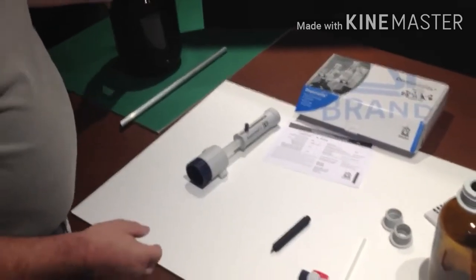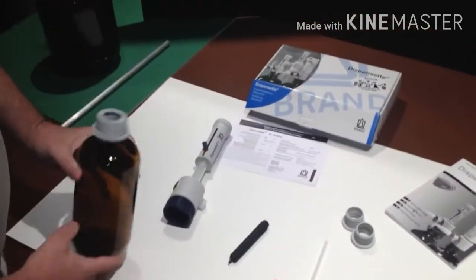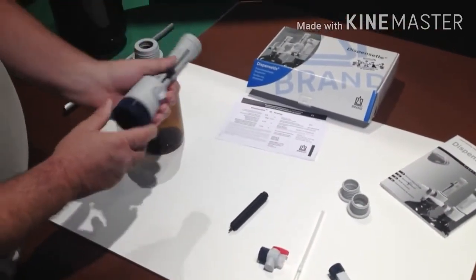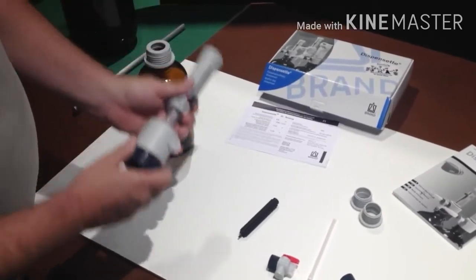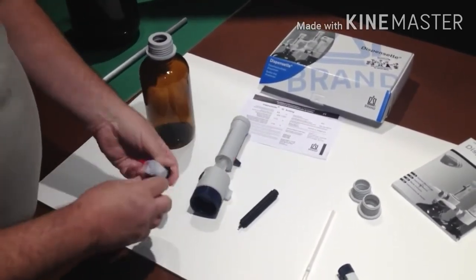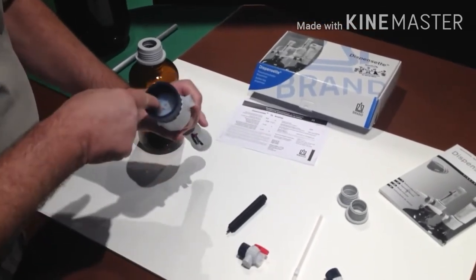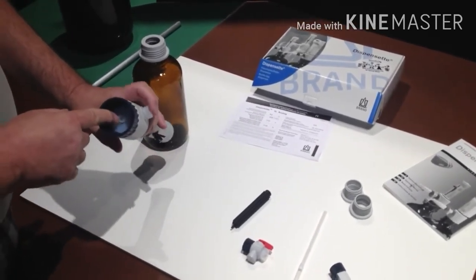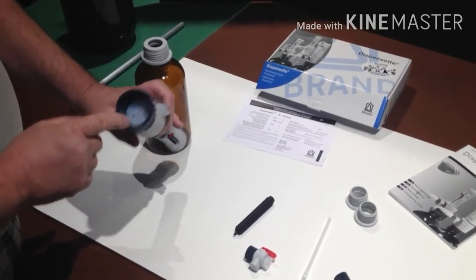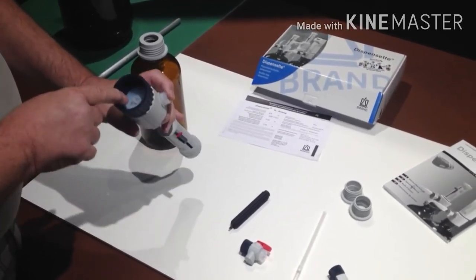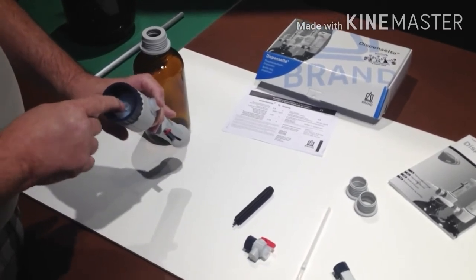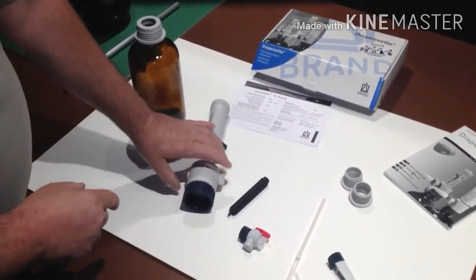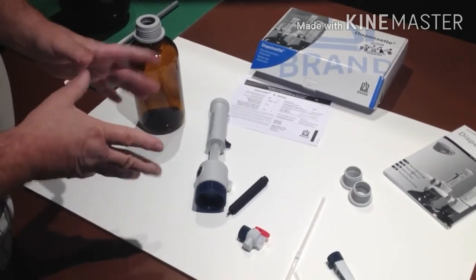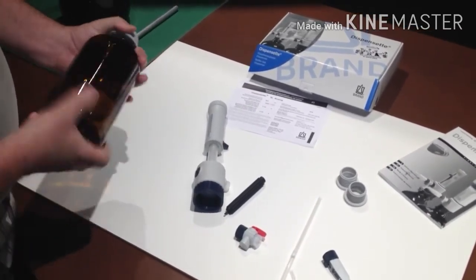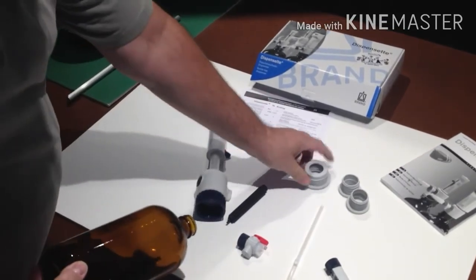A good operating practice should be, every time you finish with a bottle and it's empty, you should flush the entire system with hot water to clear out anything that may be sticking in the valves located in here and in here. These are little metal ball bearings, and they will stick to the Teflon depending on what materials you're using. What you need to do is flush between bottles with boiling hot water. This will allow the unit to clear any sticky materials left in it, so that when you reinstall your unit, you're installing with fresh units and everything's working properly.